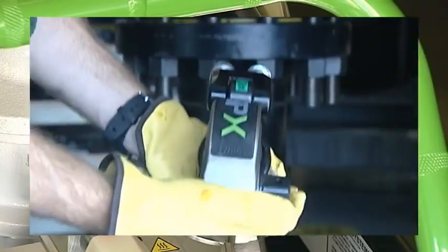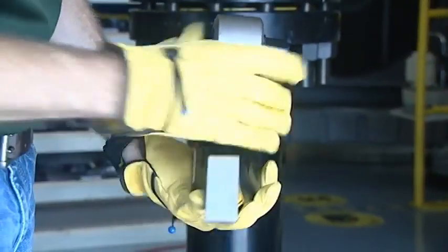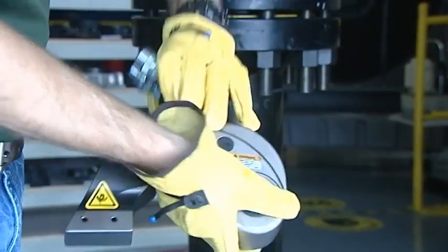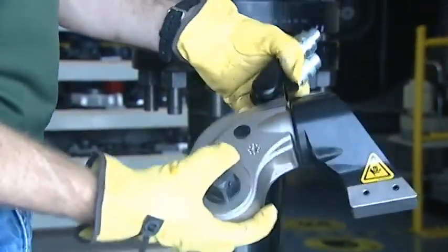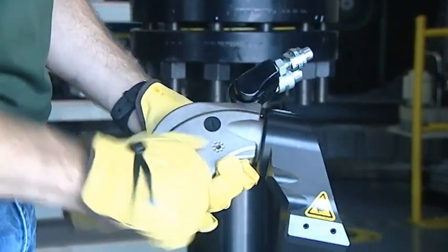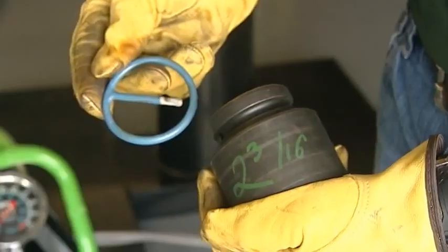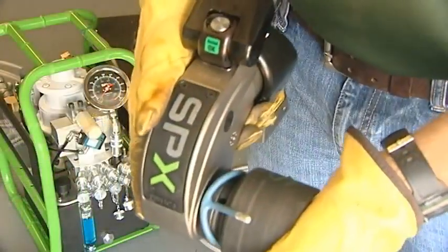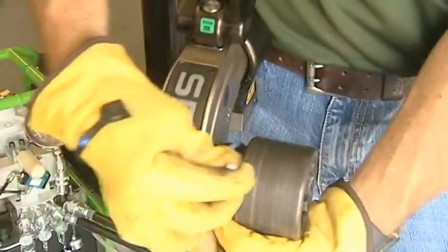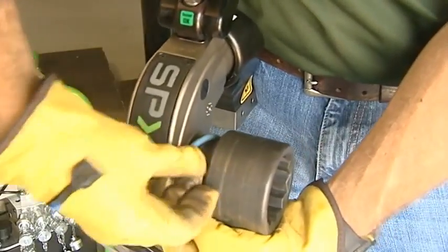When using a square drive style tool, inspect it just as you did the low clearance tool to ensure its safety. Confirm the nut size to make sure you have the correct socket and attach the socket using a pin or O-ring to secure it so the socket will stay properly attached to the tool.